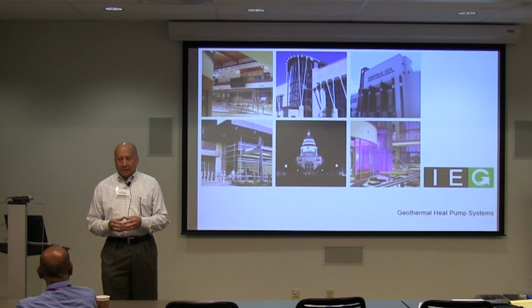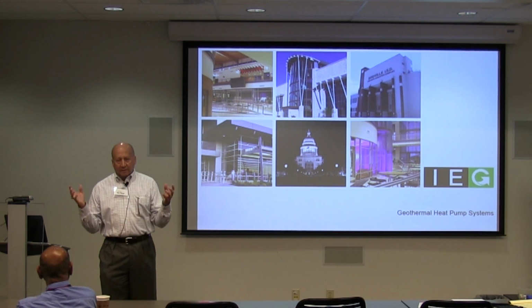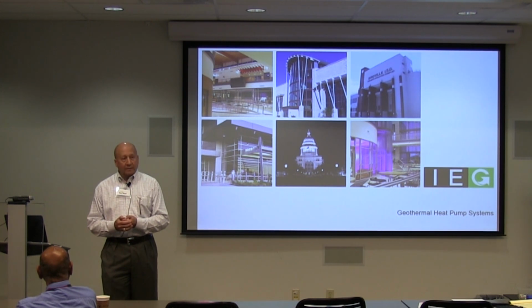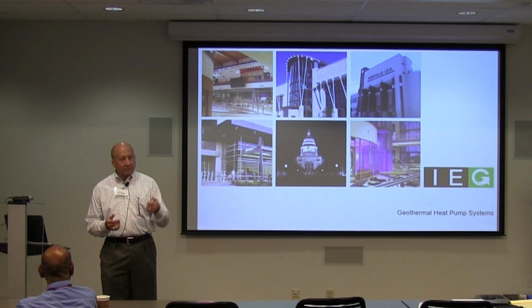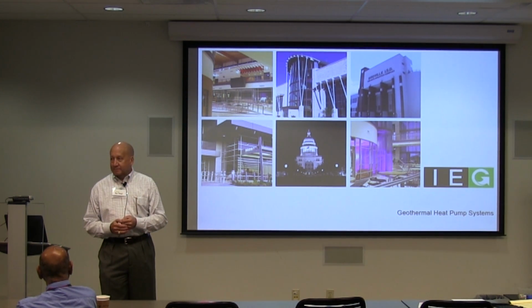Stats showing 77 and it's 72 in there, and this thing's running all day long trying to get to 72, which is now really 67. It wasn't designed to do that. Every control company will tell you this. I just had Honeywell tell me that in New York: 'oh, we use the best sensors out there, 30,000 ohm,' and sure enough they said, we've never calibrated these. I said, well, you're going to calibrate these. After it was over they said, wow, we didn't know that, we've always been told the head office says they don't need to be calibrated.